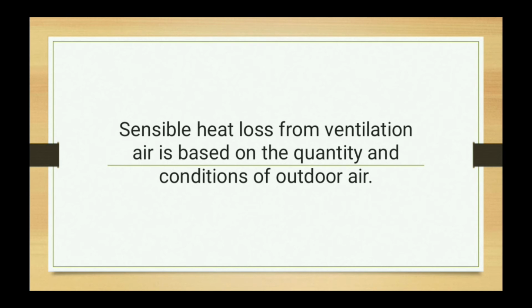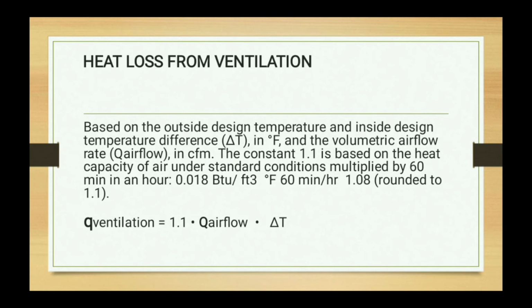Sensible heat loss from ventilation air is based on the quantity and condition of the outdoor air. So, the sensible heating load daw from ventilation ay makukompute sa ganito. Based on the outside design temperature and inside design temperature difference, delta T, in degrees Fahrenheit and the volumetric airflow rate in cubic feet per minute, the constant 1.1 is based on the heat capacity of air under standard conditions multiplied by 60 minutes in an hour, 0.018 British thermal unit per degree Fahrenheit, 60 minutes per hour, 1.08 is rounded to 1.1. So, ito yung formula ng ventilation. Ventilation is equal to 1.1 multiplied by airflow multiplied by delta T.